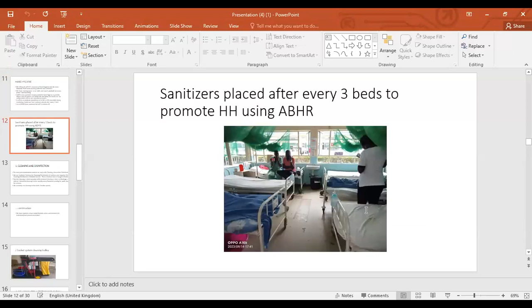Next is cleaning and disinfection. For the decontamination processes, we ensure that we follow the cleaning and disinfection or sterilization protocol. For all our critical, semi-critical, and non-critical medical devices, we follow the WHO stipulated guidelines on decontamination. The word decontamination covers both cleaning and either disinfection or sterilization. We also do surface disinfection using the recommended solutions. We have detergent disinfectants, and we also have detergents. Even though the World Health Organization recommends use of detergents in cleaning, it does not recommend use of disinfectants during cleaning. But there are detergent disinfectant solutions, especially the quaternary ammonium-based compounds, where you need only one step, not 2 steps.